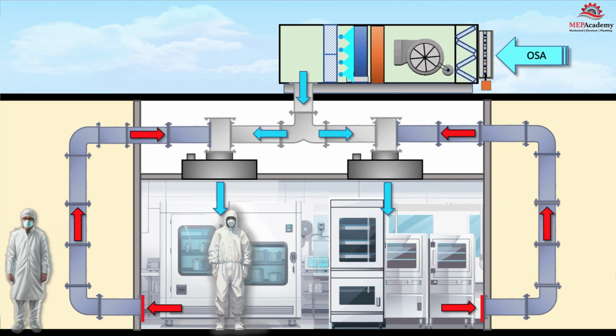Air distribution. The clean filtered air is then discharged uniformly and evenly through the outlet of the FFU. The airflow pattern depends on the specific design and installation of the FFU, which can vary based on the requirements of the clean room or controlled environment.